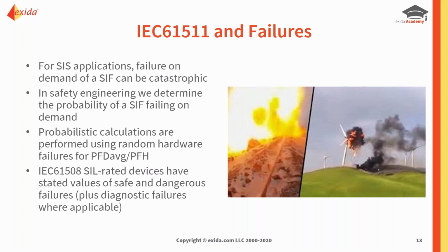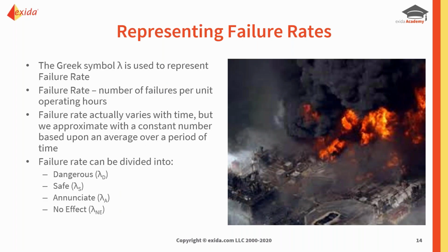This information is usually in the safety manual, but also you'll find it from the exida point of view. If you go to an exida certificate, on the second page you will find the failure rates. So these are available, so you know what they are. If you're using exSILentia, that information is already in the tool. So if you're using a specific manufacturer's device, then that device's failure rates are automatically in the tool, and when you select the device, the tool automatically uploads those failure rates.